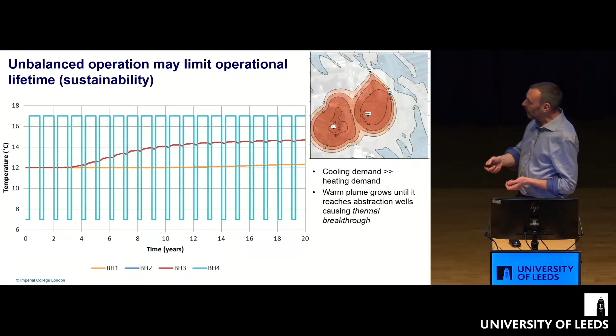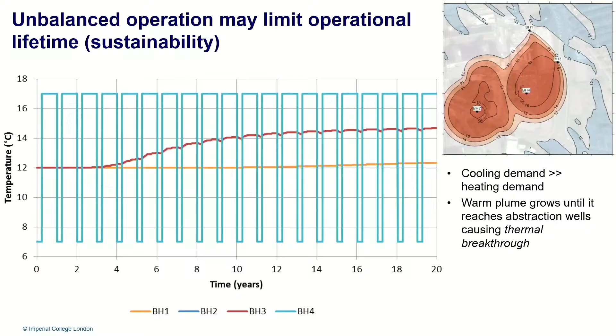This is the temperature of the production wells. So this system is providing essentially a lot of cooling, but the problem now is the production temperature is starting to increase. We're now making our heat pump do more and more work because it's taking warmer and warmer water in and having to drop its temperature. This is a system where we've had thermal breakthrough, and it reduces the efficiency with which we can provide cooling or heating.